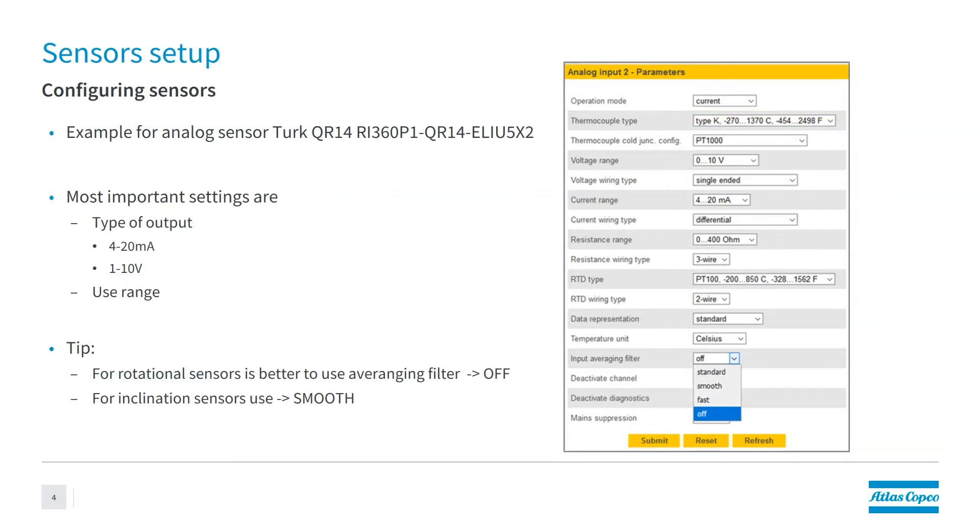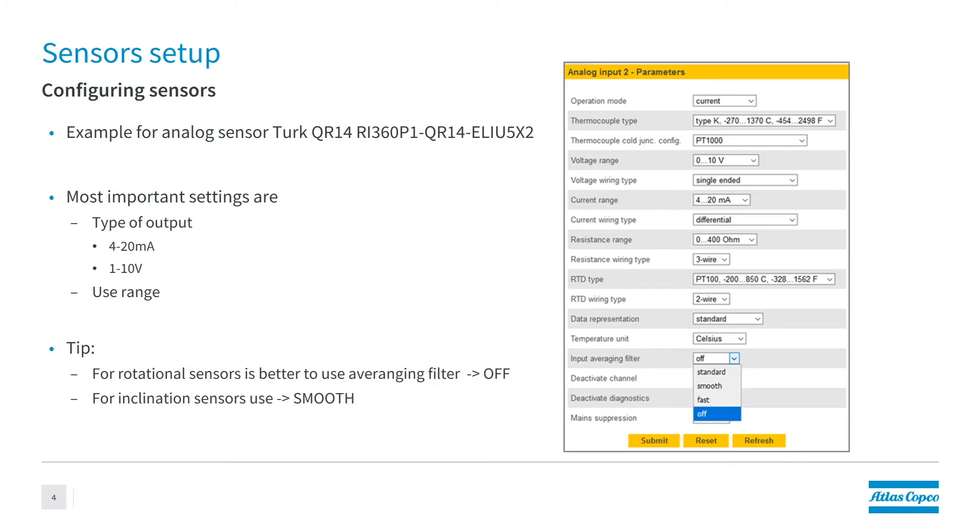So basically, you're going to leave everything pretty much exactly how it's going to be from the default purpose of the encoder block. But once you get down to the input average filter, there is something here that you really do need to do, which is if it's a rotational sensor, so we're talking about the AX1 SMS or SML, you're going to put this to off. But if you're talking about an inclination sensor, which is in our SMC POSI 3 arms, you're going to want to put this as smooth.